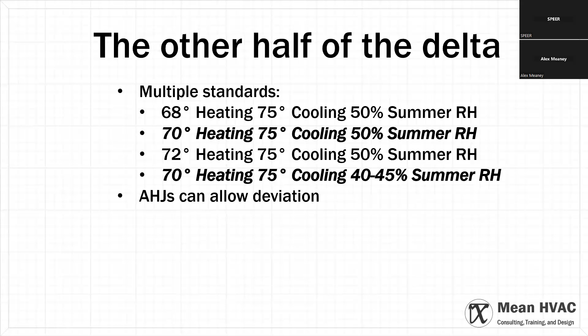Let's see. Oh, I think I duplicated that slide there. It's really simple. It's the design temperatures, right? And it gives me the TD, the temperature difference, right? So whether it's the outside temperature or the inside temperature, that is what's going to impact the load. And when you're evaluating differences, this is the mistake that Connecticut made. They looked at their design temps and they went, oh, it's only going from 84 to 88 degrees or whatever. No, it was 84 to 92. I don't know, whatever that range was. They thought it was a small percentage because they were comparing the 90 or the 84 to the number of degrees they were changing. No. It's the delta, right? It's the delta T. That's your big number right there.